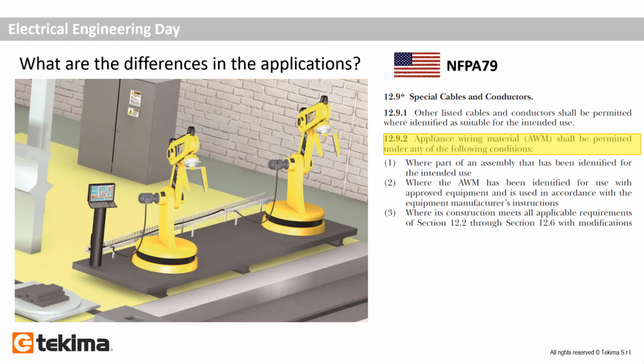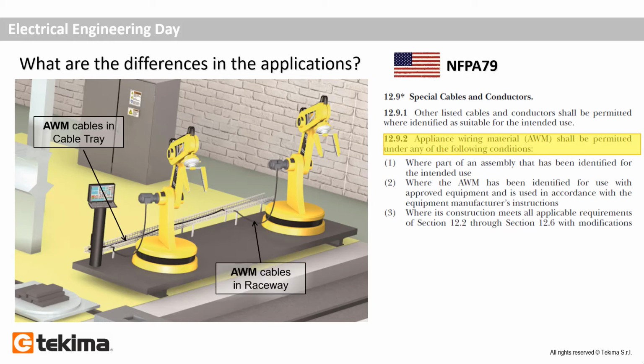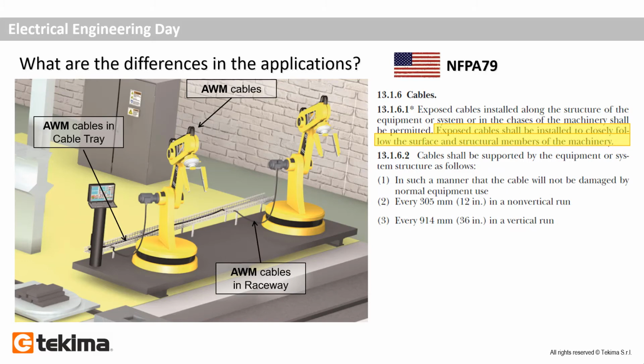Just for instance, on the machinery we can use AWM cable with UL or CSA recognized markings in the cable tray, and AWM cable between the cable tray and the equipment, but protected in the raceway. There is an exception. I can use AWM cables without any protection, just if they are followed and fixed over the structural part of the machine.